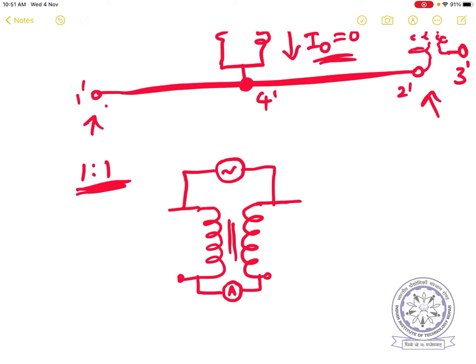Since the turns ratio is equal in this 1:1 case, whatever current I flows into the primary, the same current comes out of the secondary in opposition. Therefore, the net flux phi is zero. Note this is not the same as normal transformer operation — here we are not applying any input voltage to the winding; we are only allowing currents to flow. Since currents are equal and opposite, flux cancels out completely.